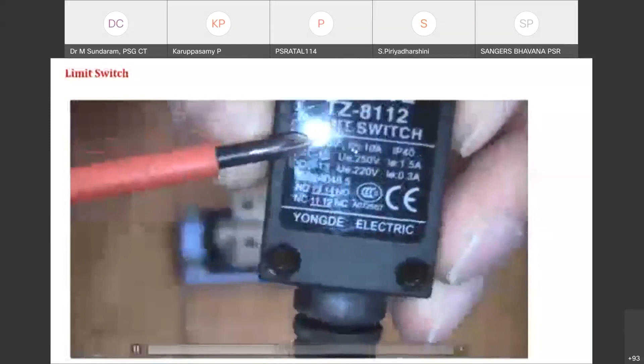And there are two current ratings with respect to AC15 category and DC13 category. This is most important. Sometimes this limit switch is capable to operate at 1.5 ampere, but if you use the same thing in DC13 category, its operating current is several times lower, only 0.3 ampere. So if we fail to select properly, then it will lead to a major accident, right?